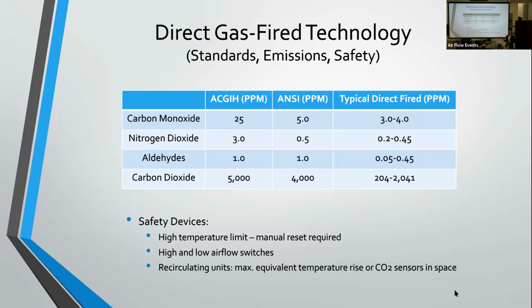On recirculating units, your firing rate is actually limited based on how much outside air you're bringing through the unit. As you reduce the amount of outside air, your allowable firing rate gets reduced. There's also a different way of limiting firing rate, based on a CO2 sensor in the space. If your CO2 levels start to exceed those maximum values, you have to limit your firing rate. Typically it sets the unit down into low fire until you're out of an alarm type of condition.